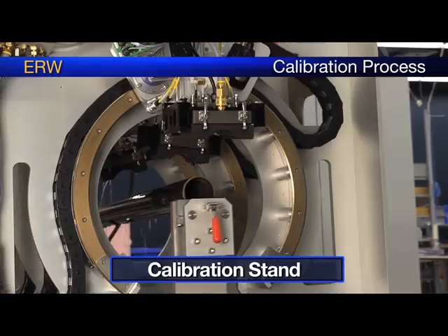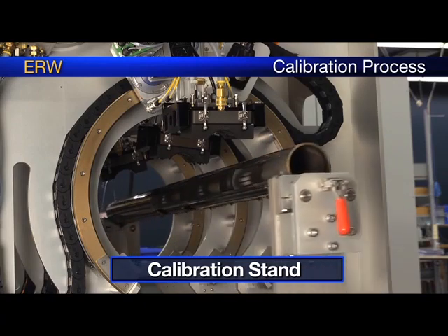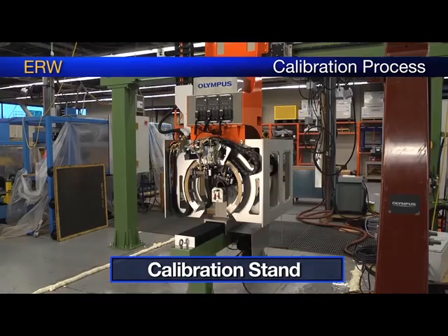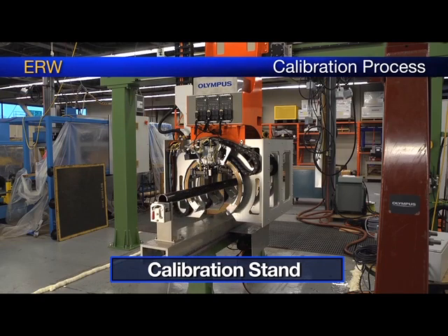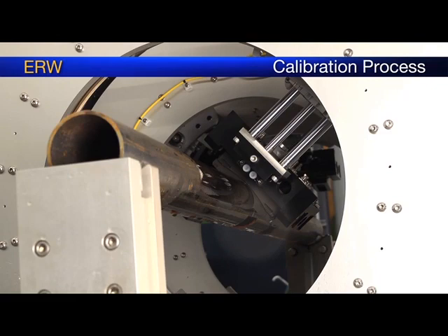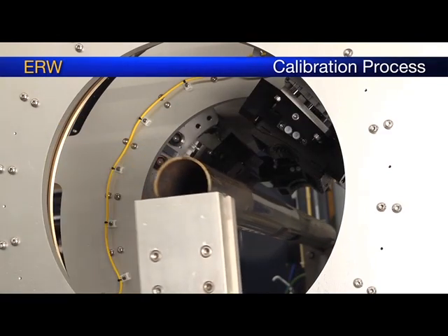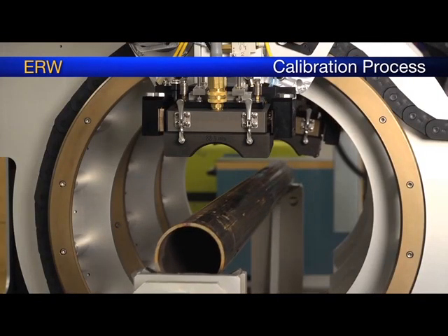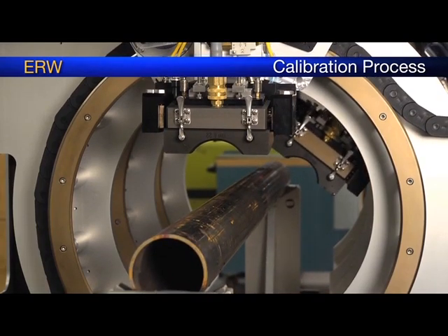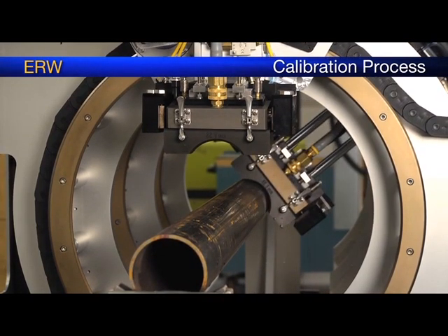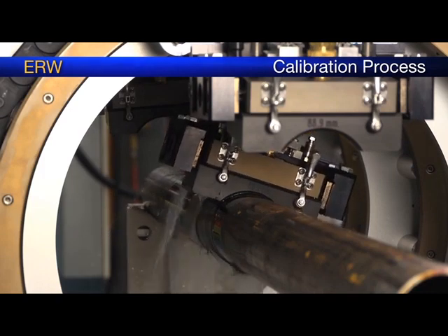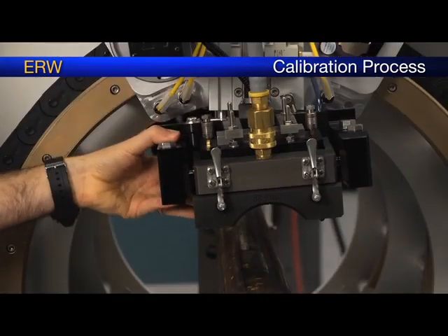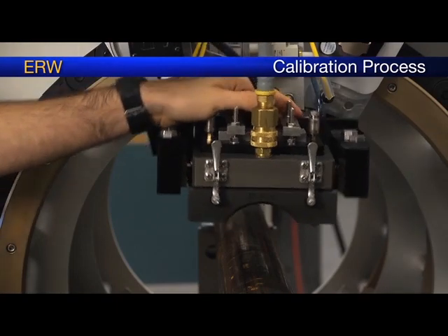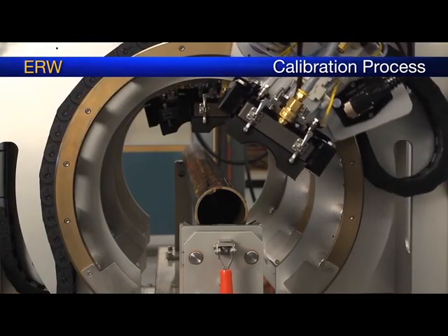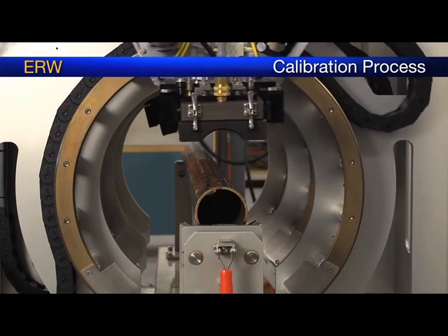As part of the system, we also find the calibration stand. The calibration stand is used in 2 very important sequences for the inspection system: for calibrating and checking the calibration. During the calibration process, the calibrator is going to position the defect that we are going to calibrate precisely under the probe. Probes are rotated around the reference notch. This allows all apertures on the probe to be adjusted at the same sensitivity level.